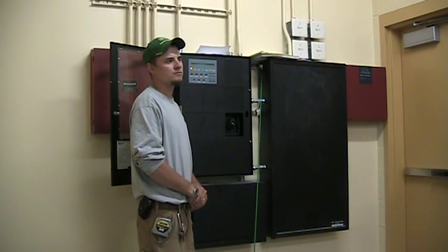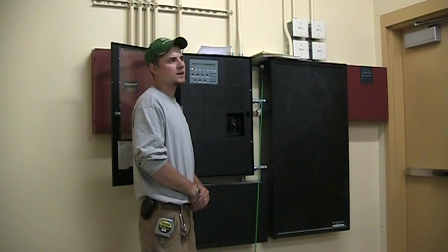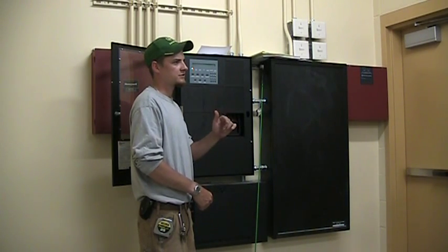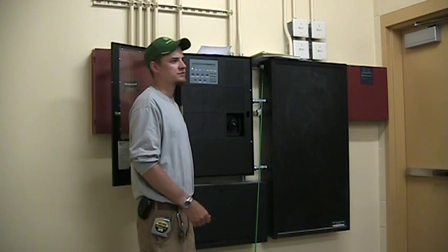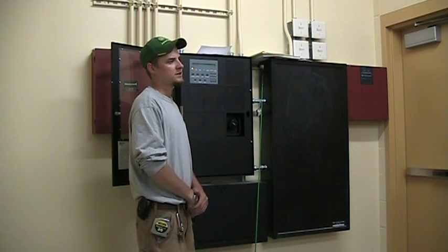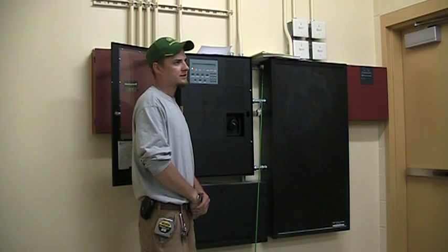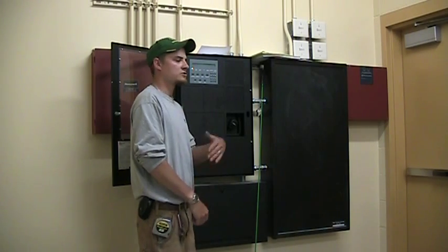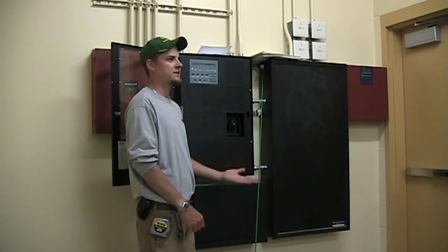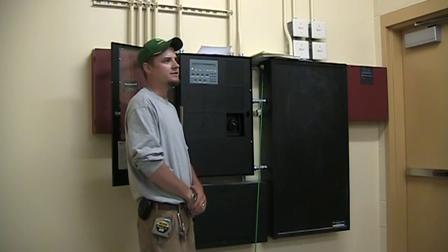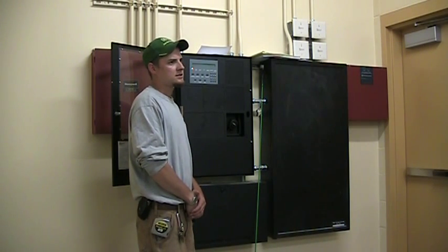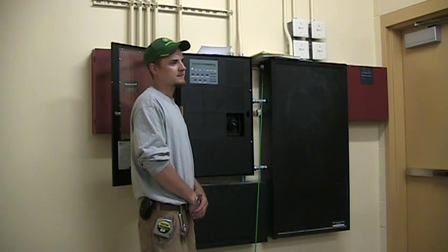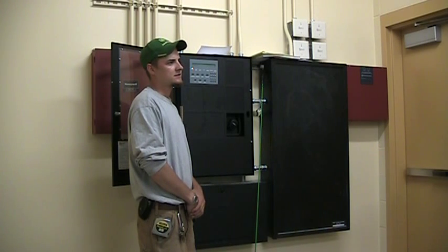I'm assuming there's just a spring-loaded button behind that. It's a toggle switch. So you would just flip it back up, close it up, and you can reset it. Once it goes to alarm, to get it to clear, you have to reset the system. A trouble will clear itself. Some of the newer ones, when you pull it down, the button pops out. This one's got the toggle.